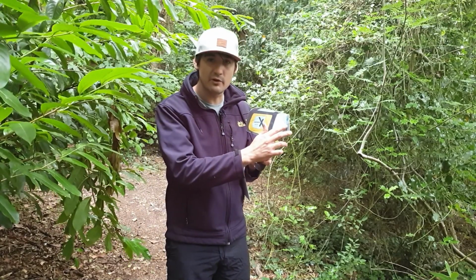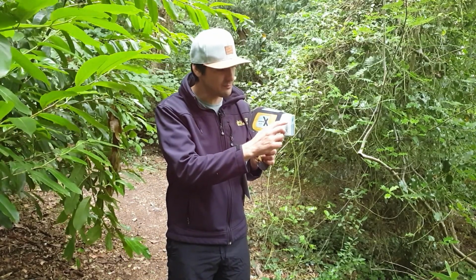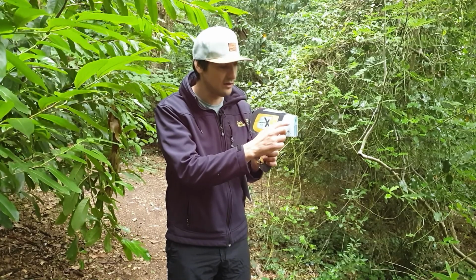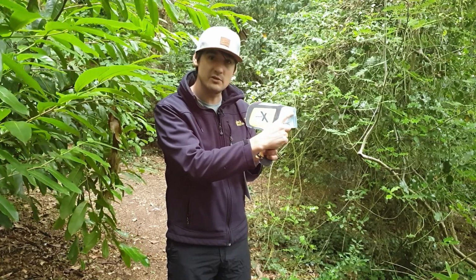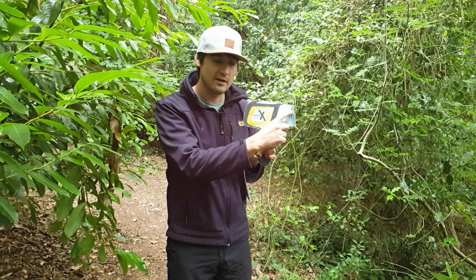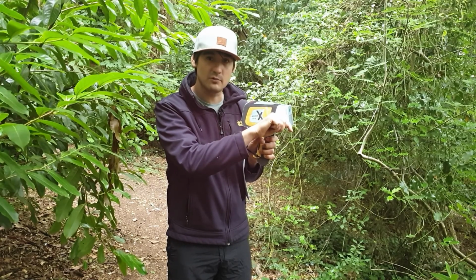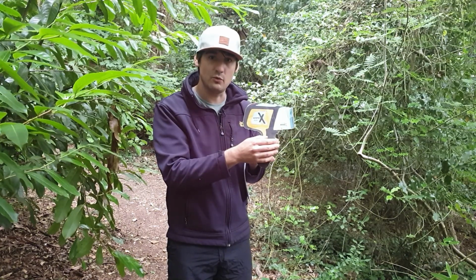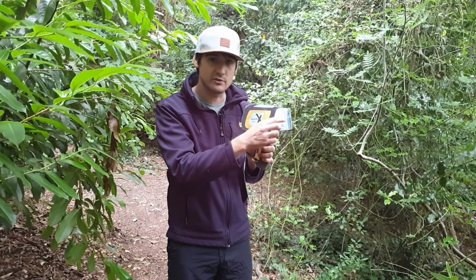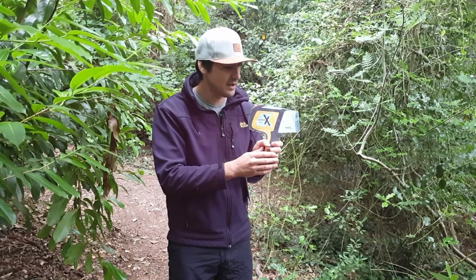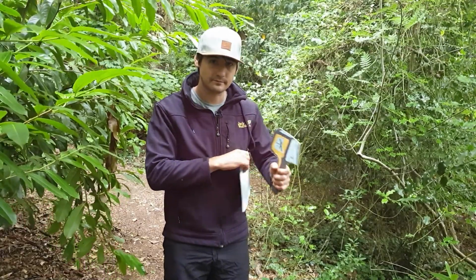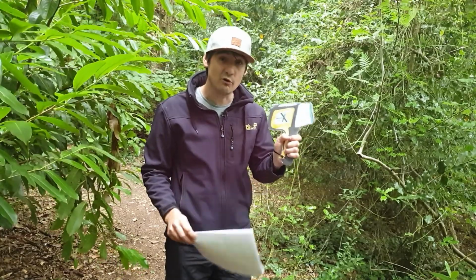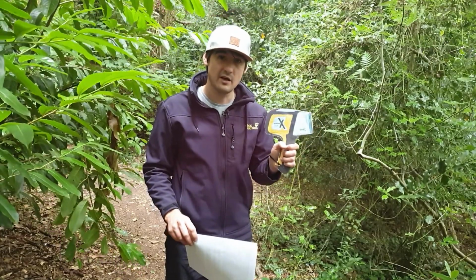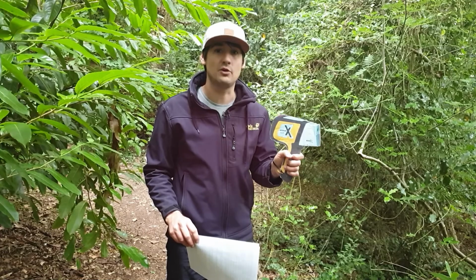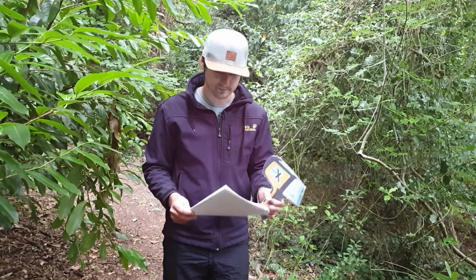If the window is broken, then you simply need to replace the polythene window by undoing the top 2 screws on the XRF, opening the flap door and putting in a new window. Simply do up the 2 screws, being careful obviously not to lose them, and then you're ready to go again. Obviously the XRF needs to be off when you change the windows, and when you turn it back on again, you may need to do a cal check after.